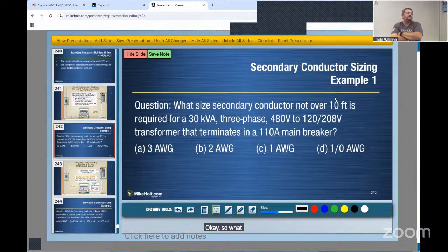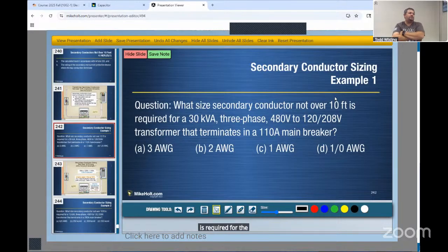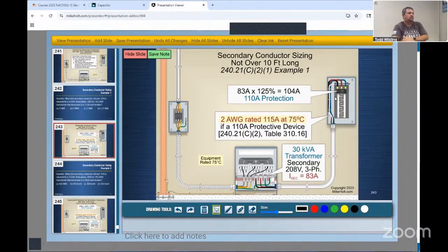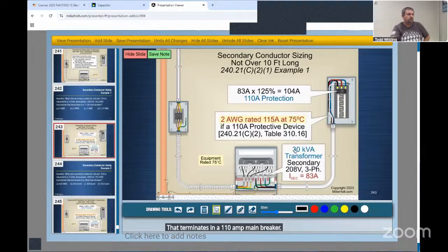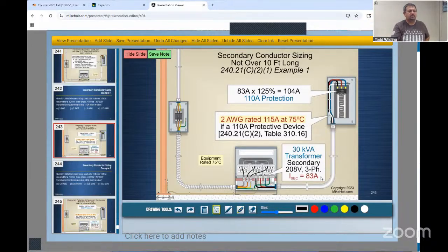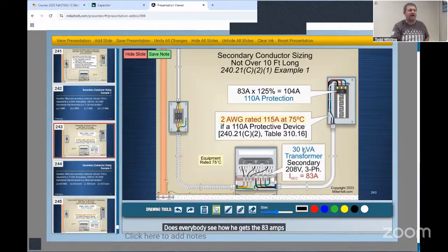Okay, so what size conductors do I need? What size secondary conductor not over 10 foot is required for the 30 kVA 3-phase 480 120/208 transformer that terminates in a 110 amp main breaker? So 30 kVA 208 3-phase. Does everybody see how he gets the 83 amps? Can I take 30,000 divided by 208? What's 30,000 divided by 208?